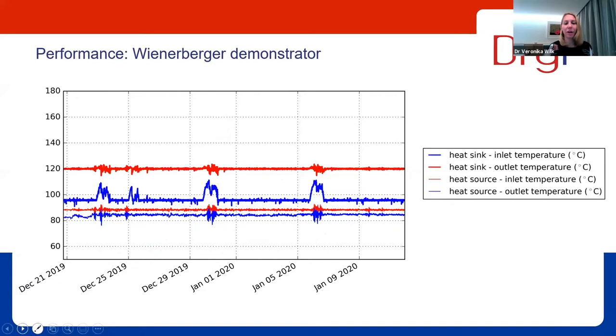Here we see a longer period. This was in December 2019, January 2020. It's 3 weeks of operation. So if we compare that to the previous figures, we have here a much warmer heat source. Here, 88 degrees were provided. And during those 3 weeks, the heat pump was operated at a heat supply temperature of 120.